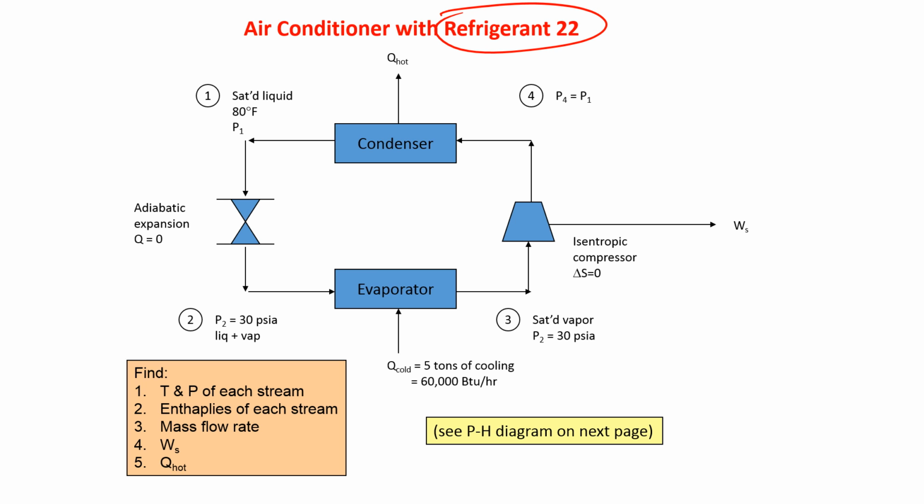Refrigerant 22 is actually a hydrochlorofluorocarbon, and it is chlorodifluoromethane. Now this depletes the ozone. It's been phased out in developed countries, but it is increasing in developing countries quite rapidly, to the point that the decrease in developed countries is more than overcome by the increase in developing countries, so the worldwide production and use of it is going up.